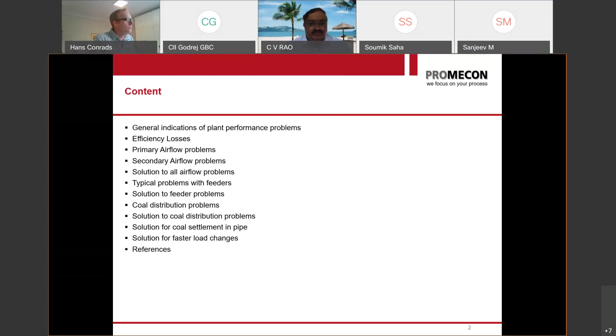And before I go into our technology, I would like to go a little bit into the current problems that you can find on nearly any boiler in the world. I have seen many Indian boilers, I've seen other Asian boilers, and they all come up with the same problems. And these problems are the reason for efficiency loss, high NOx, as well as inflexibility to run the unit up and down, for example, when you have additional renewable energy in the grid. So let's first look at a typical thing. When you look at an air heater, let's go from the back. I start from the back of the boiler and I will go up to the front of the combustion to find the problems, the reason for the problems.